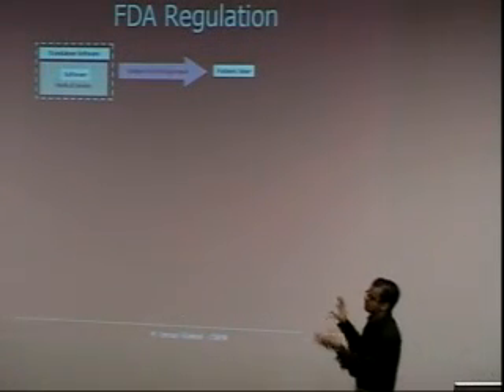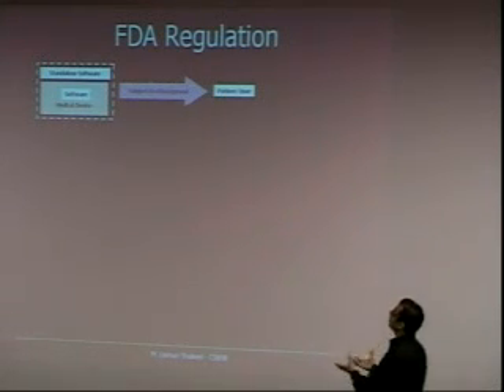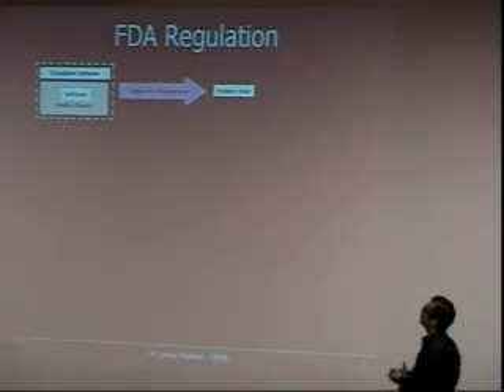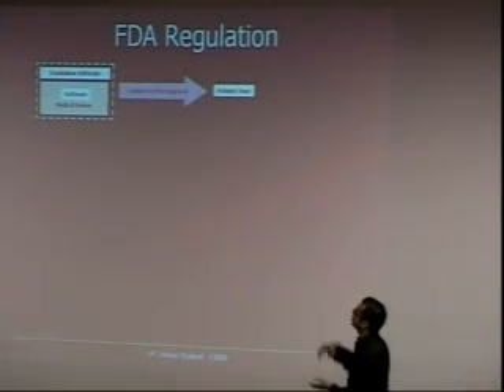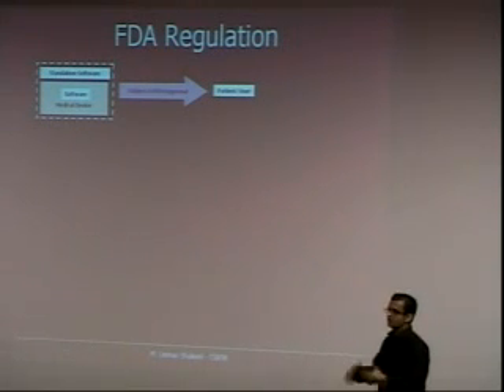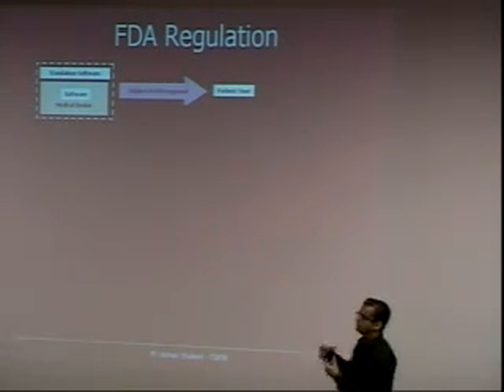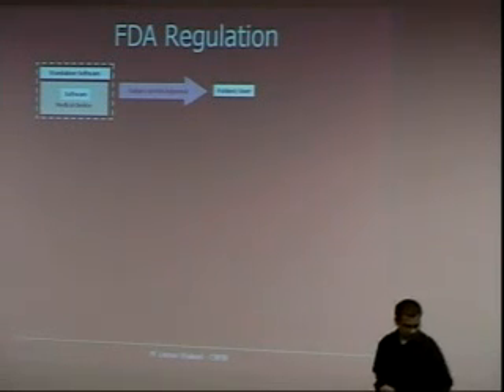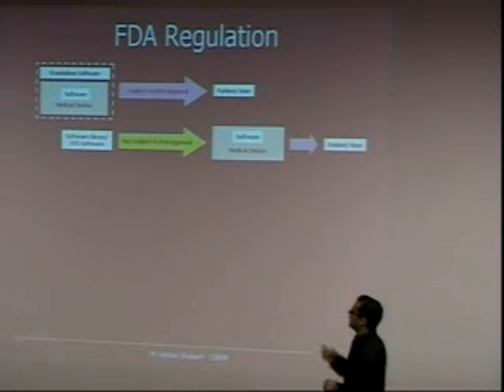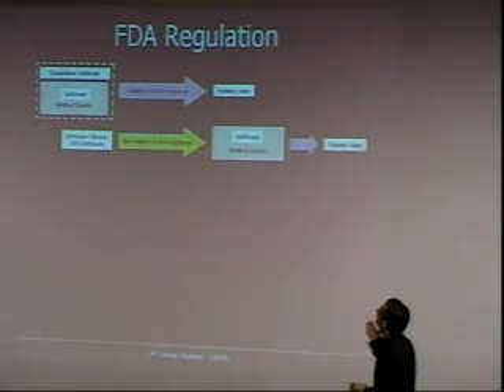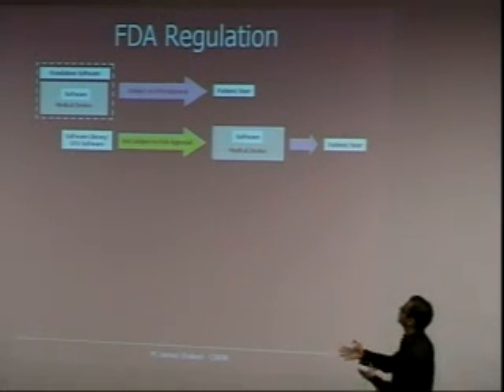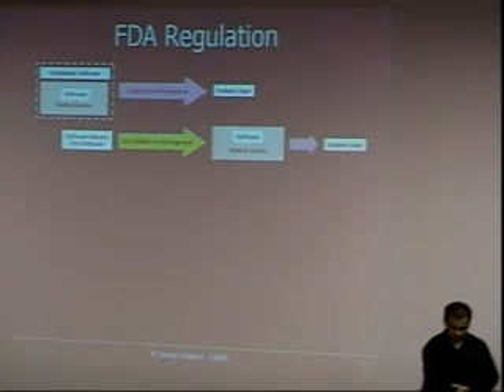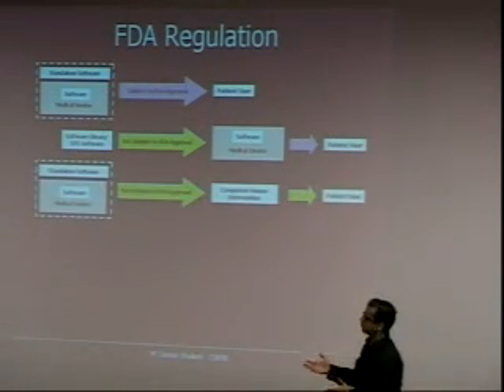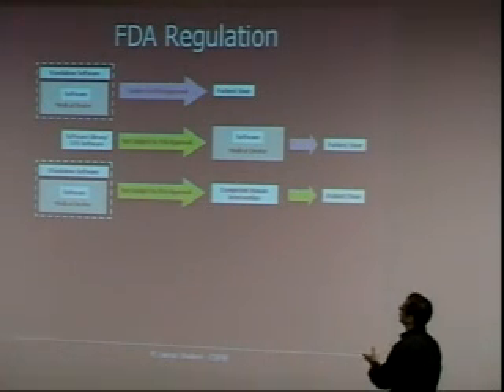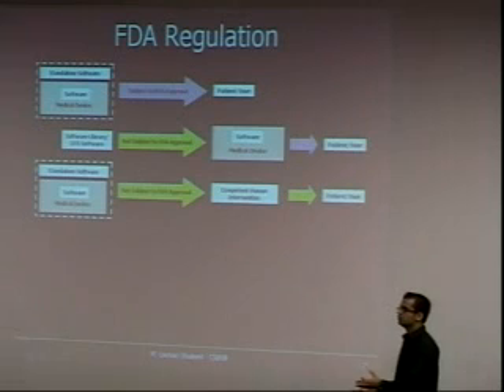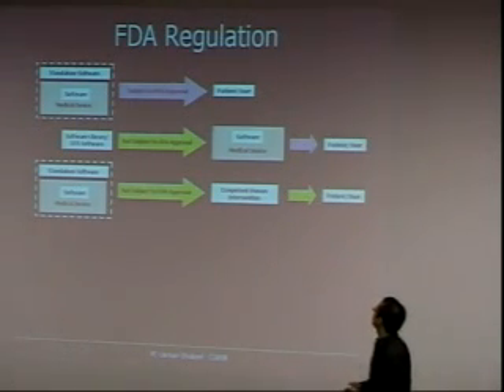FDA regulations, I'll just spend very little time explaining what devices come under FDA regulations. Basically, first of all, a medical device, or software used in a medical device, or a standalone software that has a direct impact on the health or life of a patient or a user, is subject to FDA approval. The second category can be a software library or off-the-shelf software, which is used essentially to create the software for a medical device. It is not subject to FDA approval. And the third category is a standalone software or software medical device that is subject to competent human intervention, let's say a certified individual who is operating that machine. We don't need an FDA approval for that.